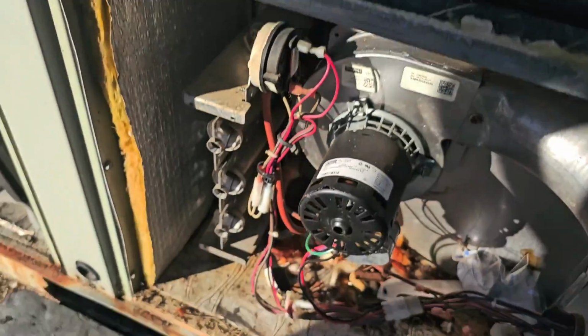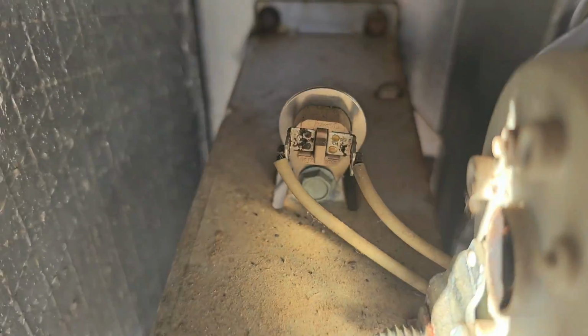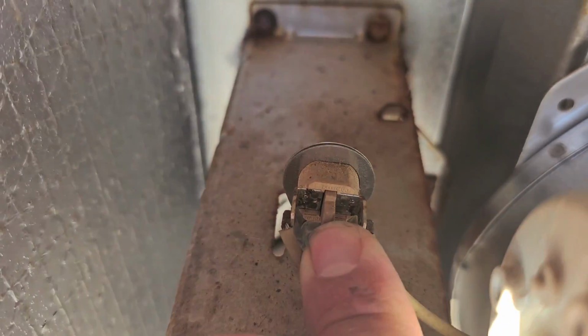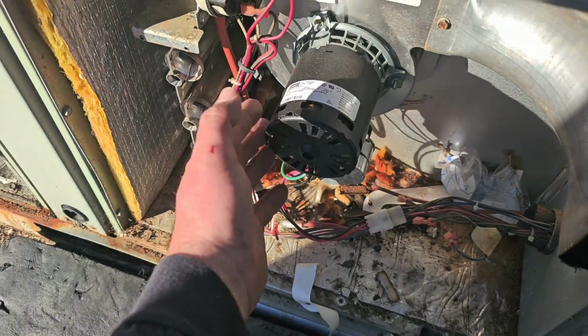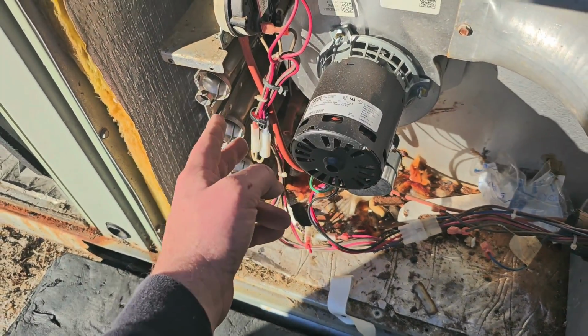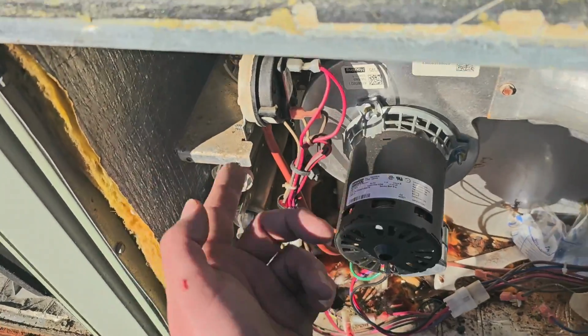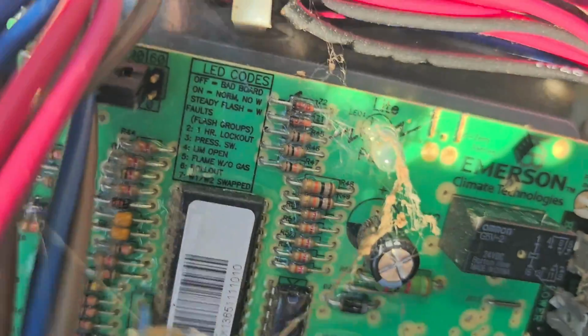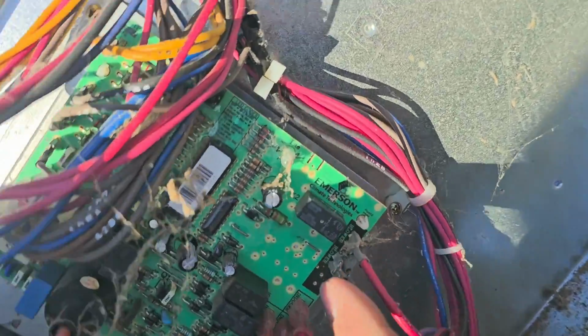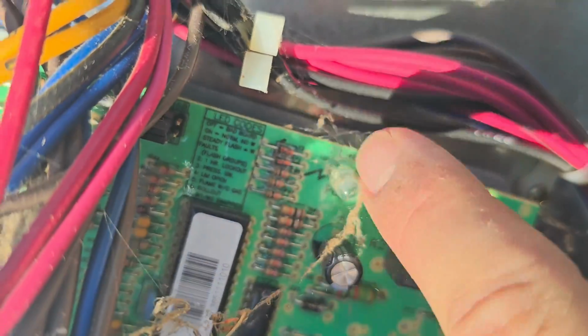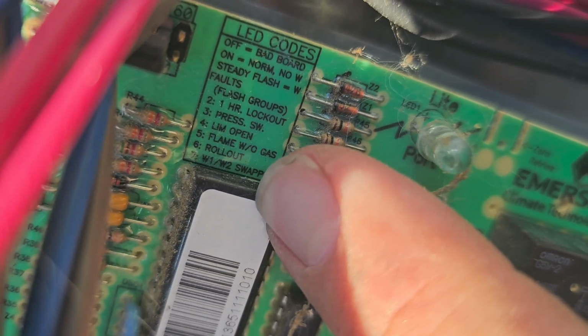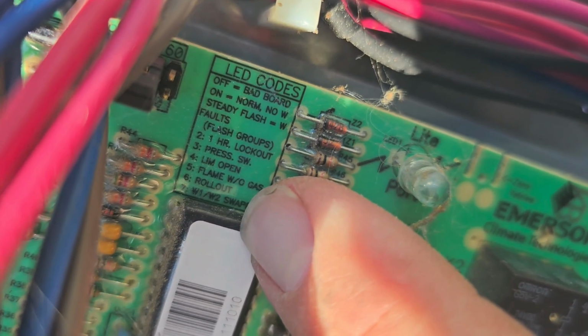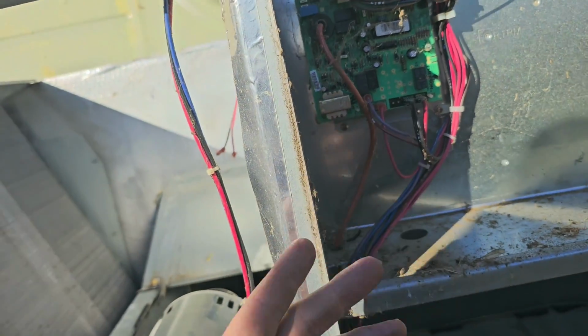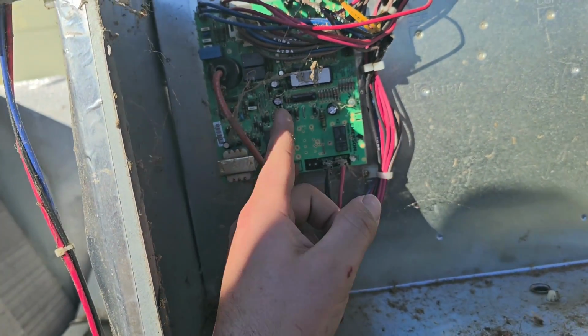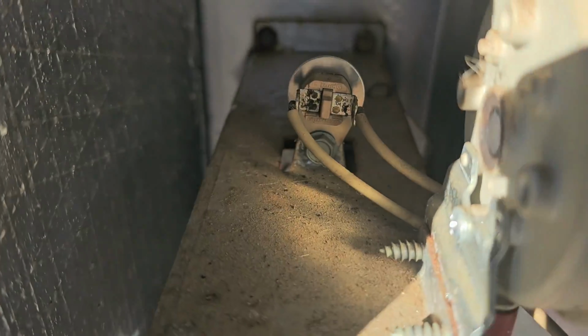When the heat exchanger's busted, the flame will roll out. This right here is the rollout switch. And I found this switch open. So I had to push the button to get the unit to retry and to get the burners to light again. So I knew that I had to check the heat exchanger. And that's the reason I checked the heat exchanger. Also, this is the ignition control board right here. And it will display a fault code right here where this LED light is. And it was flashing 6 times. You can see where it says rollout. So I knew to check the rollout switch because I had 6 flashes on my ignition control board.